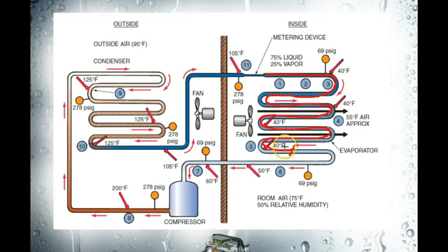And at some point near the end of the evaporator coil, all the refrigerant has boiled off, and then it's all vapor. It drops off of the pressure temperature chart. It's not at a saturation temperature anymore, and now the vapor starts to pick up heat, and that's sensible heat, and we call that superheat. And then it enters into the compressor.